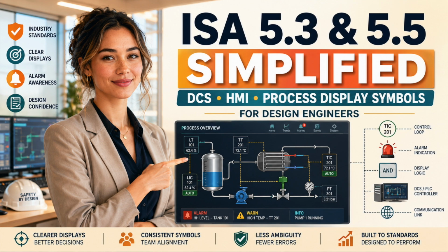Represent enough architecture to explain the control strategy, system boundary, operator accessibility, backup relationship, and critical dependency. Do not draw technology merely because it exists. Communication links should be shown when they clarify package interfaces, remote input and output, supervisory control, backup relationships, or important data dependencies. Drawing every network path creates spaghetti. Hiding every system boundary creates false simplicity. Show architecture where architecture affects understanding, failure, or responsibility.